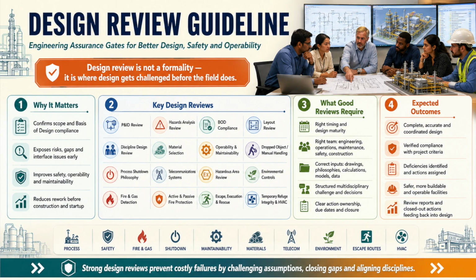The hazards analysis review then challenges the facility as an integrated hazard control system. For offshore and process facilities, the review must be systematic and multidisciplinary. It must examine process containment, ignition potential, shutdown, detection, protection, escalation, evacuation, and emergency response. It should follow completion or sufficient maturity of fire and gas cause and effect logic, hazardous area classification, shutdown analysis, escape and evacuation studies, and safety integrity assessments. The outcome is not a statement that the review was completed. The outcome is a report that identifies inadequacies, defines recommendations, assigns ownership, and records how the risk will be resolved.